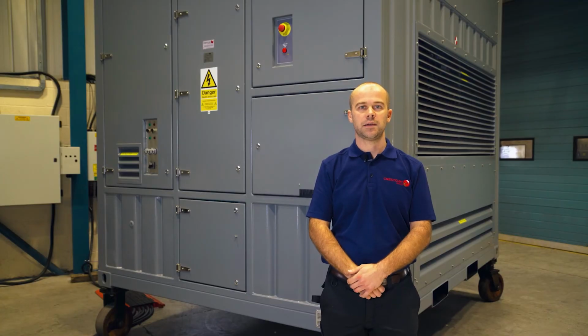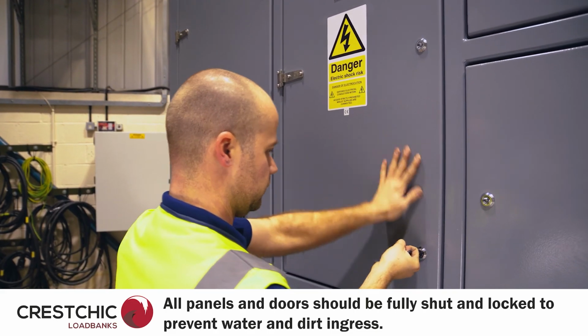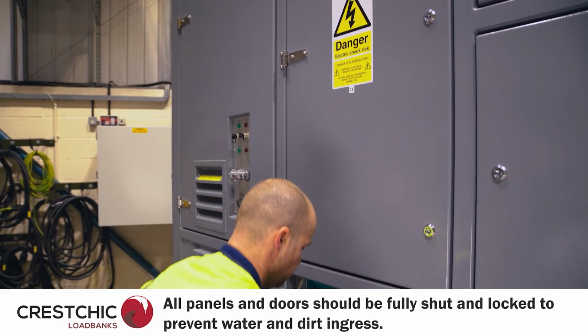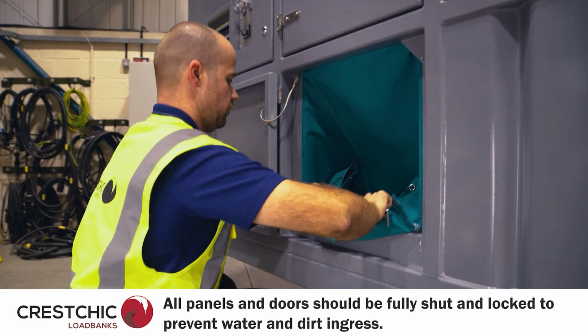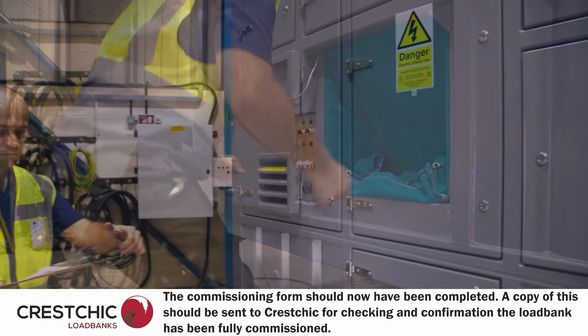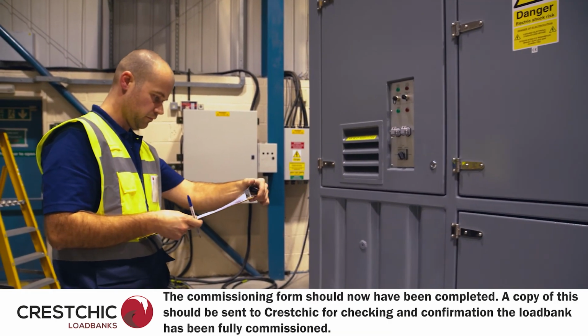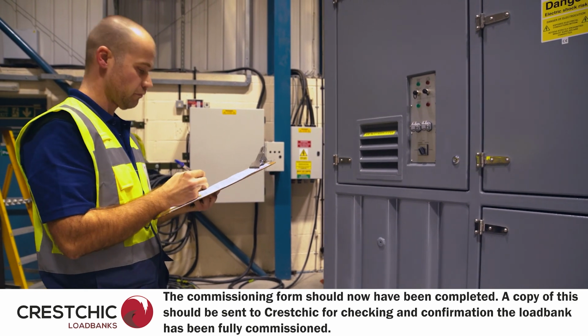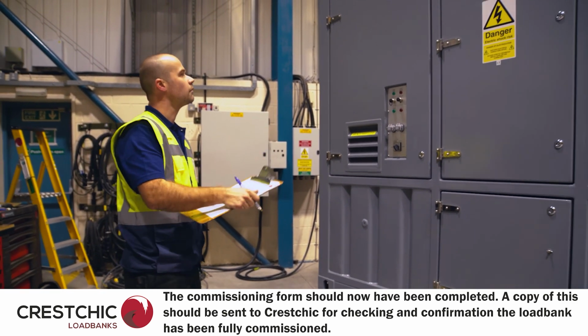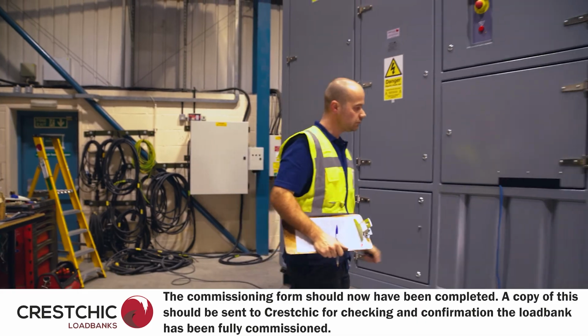If the load bank is temporarily installed, it is recommended that the control cables are put away to prevent possible damage occurring to these. All doors and panels should be fully locked after using the load bank. This is to prevent water ingress. The commissioning form should now have been completed. A copy of this should be sent to Crestchic for checking and confirmation the load bank has been commissioned.